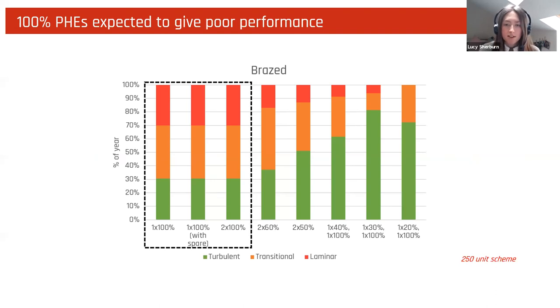So then looking more into brazed plate heat exchangers, I compared the flow regime of different scenarios. As you can see on the graph here, we had one plate sized at 100% of peak load, so your duty scenario. We had the same again, but with a spare plate located in the plant room. This was looking at the cost of that really. We then had duty standby. We then looked at duty assist approaches: two plates sized at 60%, two plates sized at 50%. We've seen these before in industry. And then we also thought to look at using almost like a jockey plate, so having a plate sized at sort of 20, 30 or 40% and then having a larger size plate as well. So what can we see from the flow regime with this?